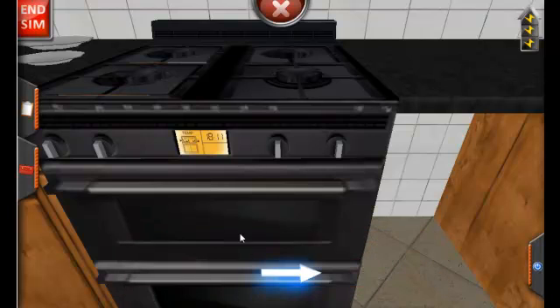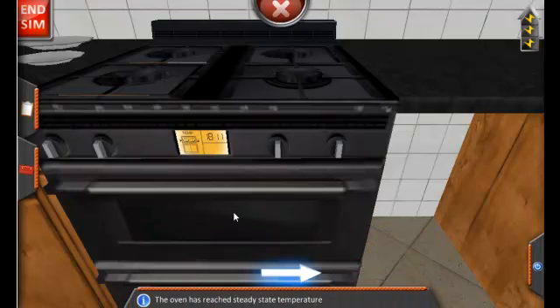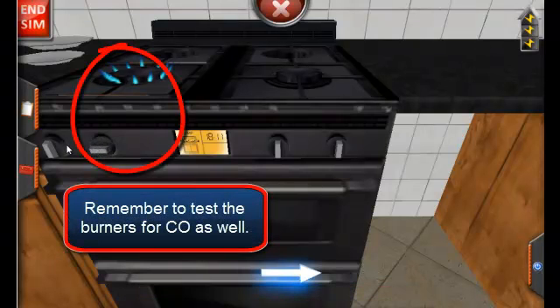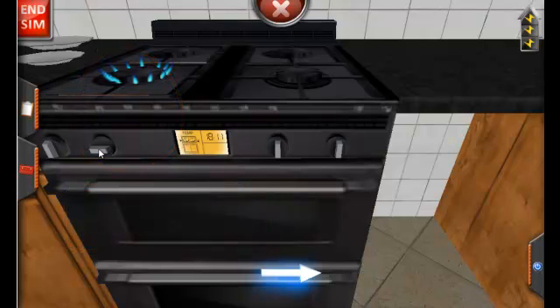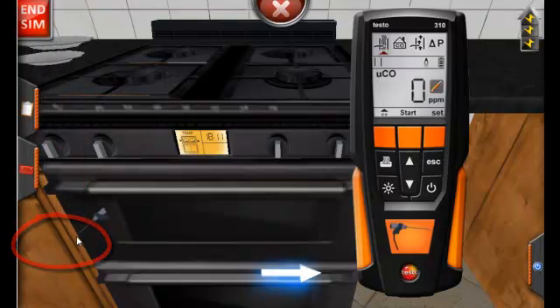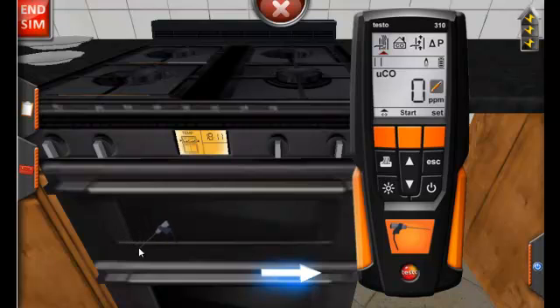The third functional piece of the oven are the burners. We will also test these for carbon monoxide. Let's begin the tests. To do so, we are going to launch our combustion analyzer. To test the flue gas levels, we want to place the probe in the back vent of the oven and set the tool to flue gas test.